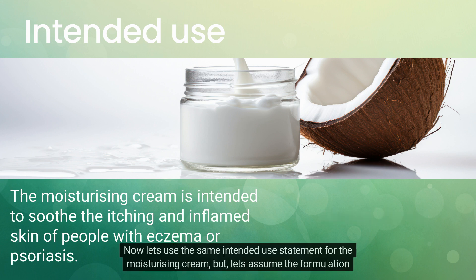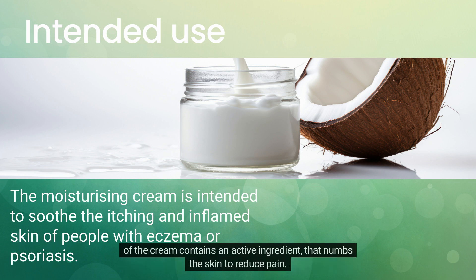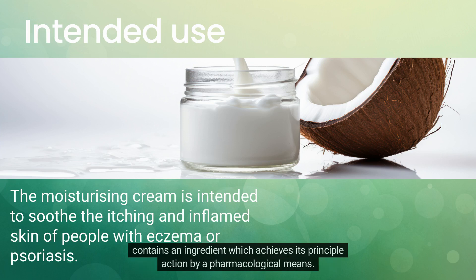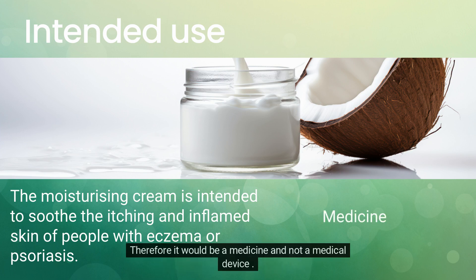Now let's use the same intended use statement for the moisturizing cream, but let's assume the formulation of the cream contains an active ingredient that numbs the skin to reduce pain. In this case, even though the moisturizing cream falls under the definition of a medical device, it contains an ingredient which achieves its principal action by a pharmacological means. Therefore it would be a medicine and not a medical device.